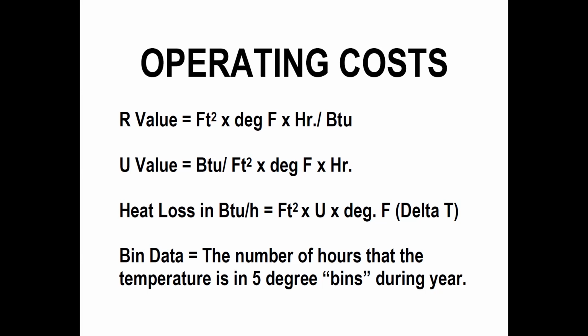The local contractors are increasingly using some sort of program that I'm going to learn about in a little while, where they just basically measure the square footage of the room and assume a worst case scenario, based on what they think how old the house is. And they say, this is what your heat loss is. And I don't really think that's a good idea. I think that one should measure it, take a good guess at when the house was built. Well, it was built in 1960, so it's probably got a 3-inch stud wall and R11 at best insulation in there. That's the sort of heat loss, heat gain that we should be calculating before we size anything.